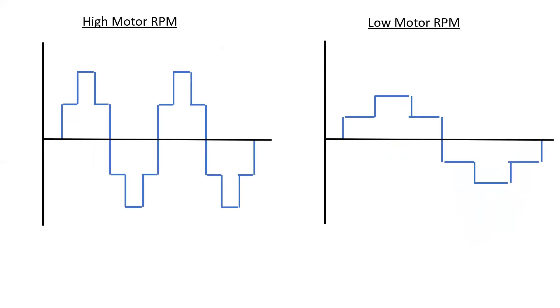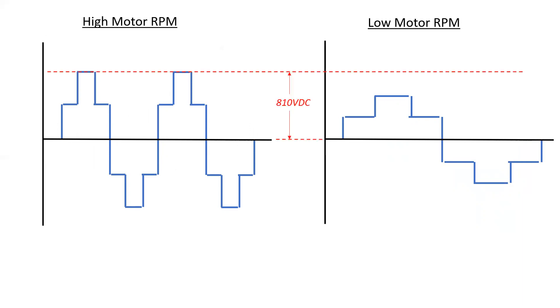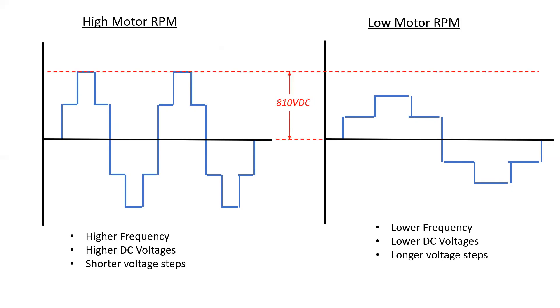For high motor RPM, we see high voltage, and the rate of positive and negative alternations is quite a bit higher. For low motor RPM, we have lower voltages and a longer spreading out of those positive and negative alternations. So high motor RPM means higher frequency, higher DC voltages, and shorter voltage steps. Low motor RPM means lower frequency, lower DC voltages, and longer voltage steps.